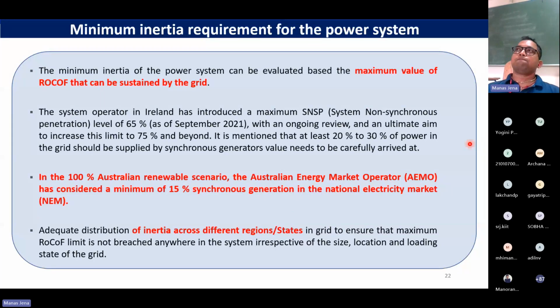So till now we discussed the impact of inertia and how inertia monitoring is important. Before we close this part of the discussion, I mentioned there are two parts: one is inertia, the other is protection. We'll take a break after the inertia part. Before taking that break, we need to understand how to address this issue. The issue is related to RoCoF and under frequency load shedding settings, so how do we take care of it? Let us have a short discussion on this.